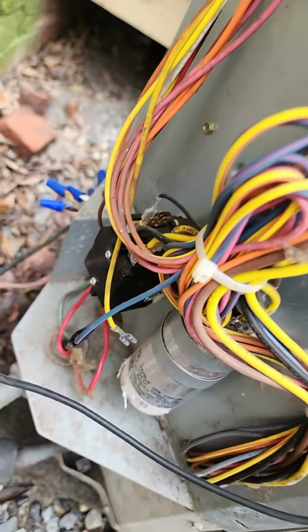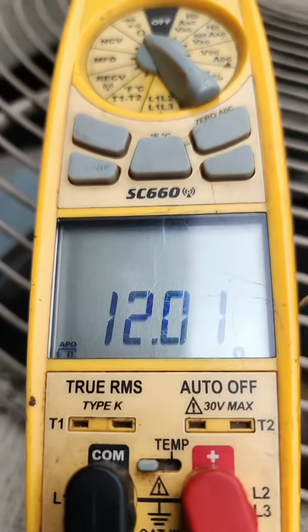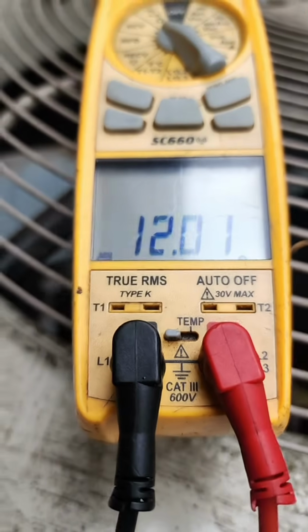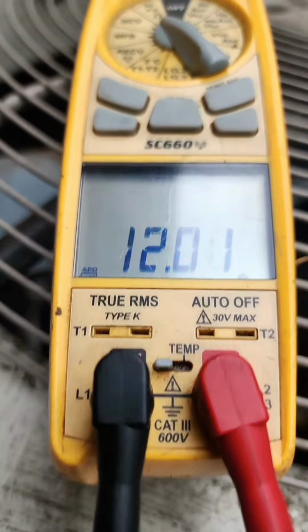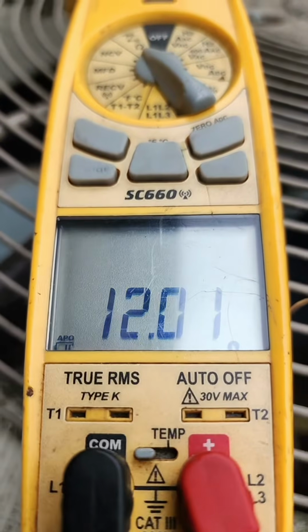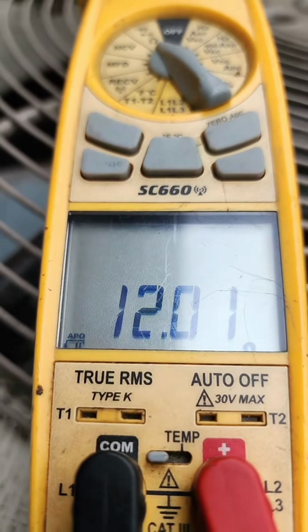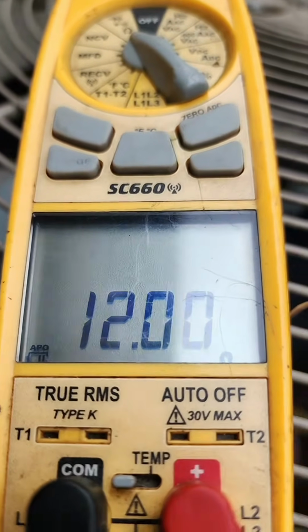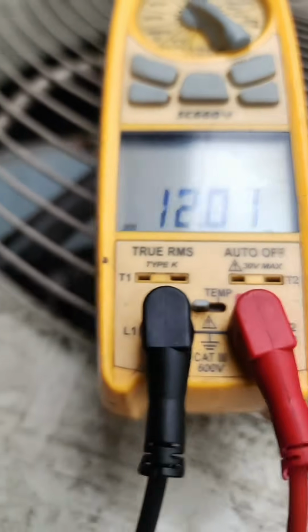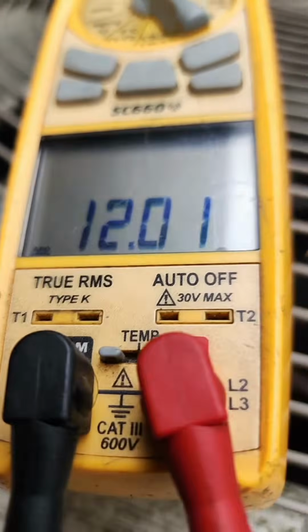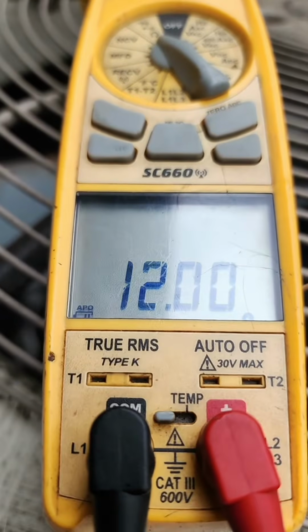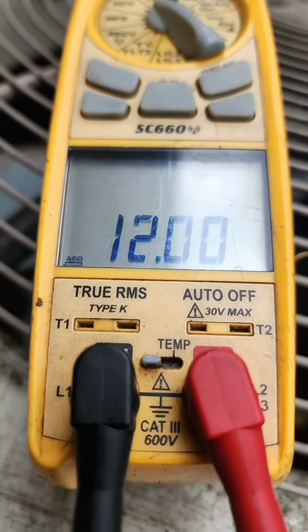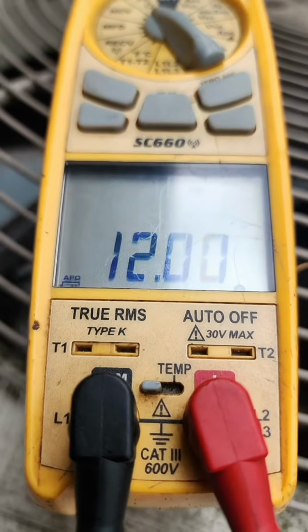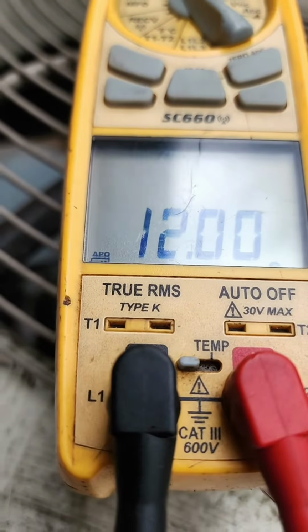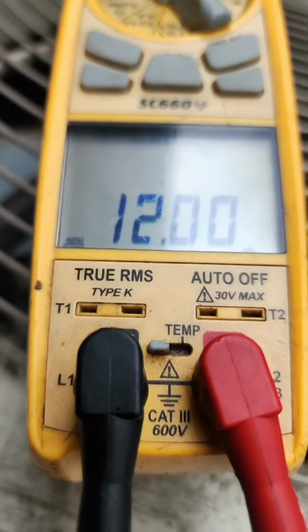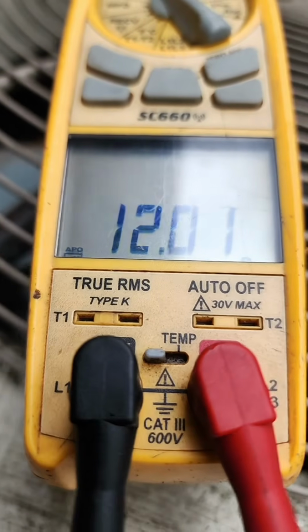We'll take this one out. We're gonna check that one. And they ain't reading pretty damn near nothing. So when you're checking it, a good coil will give you some type of measurable resistance. A short would be damn near 0. It might say like 0 point something, but it's 0. And then you'll get open line. If it's open line, it means that you think of a circle and something cut that circle in half. So it means that there's no connection. So open line, there's no connection. Short, you're gonna get 0, which typically will pop a fuse or trip a breaker. And then measurable means that 9 times out of 10 the part is good.